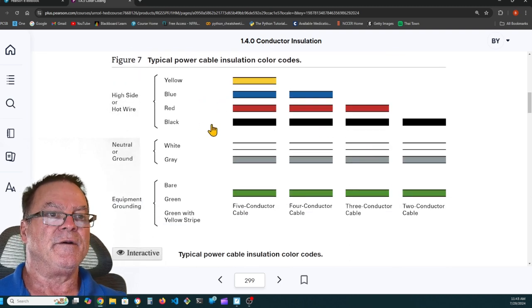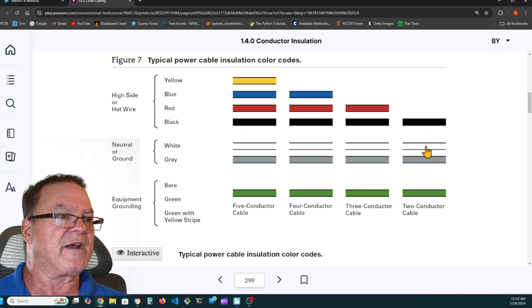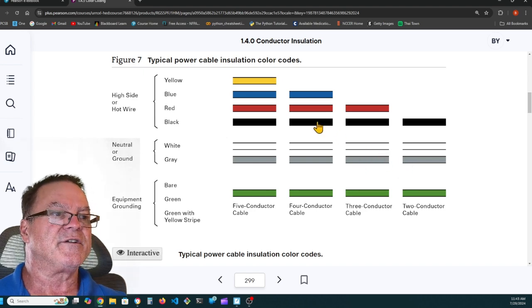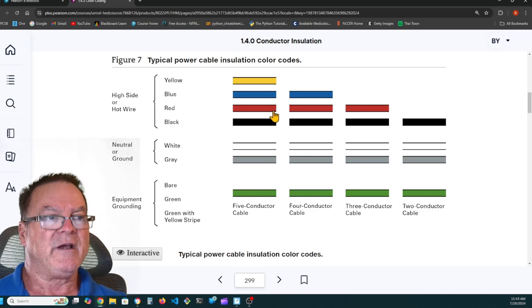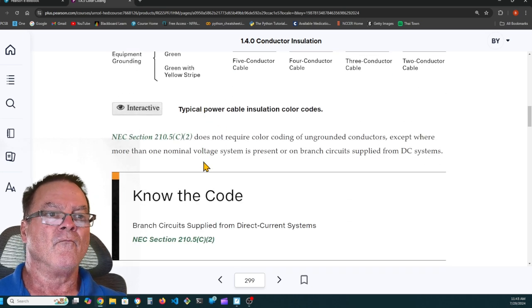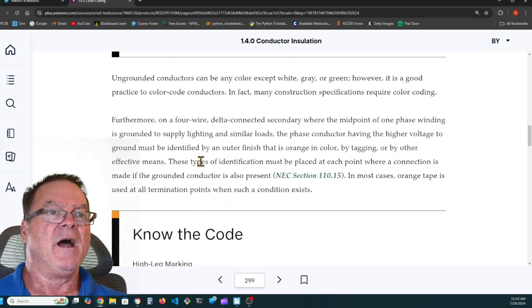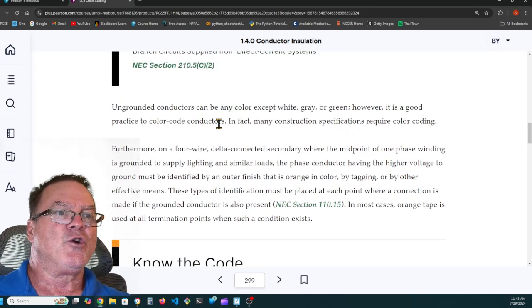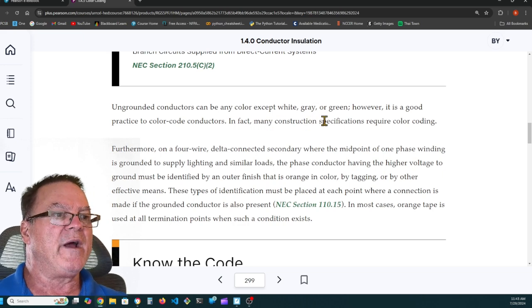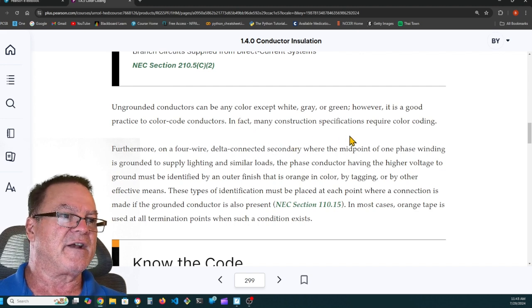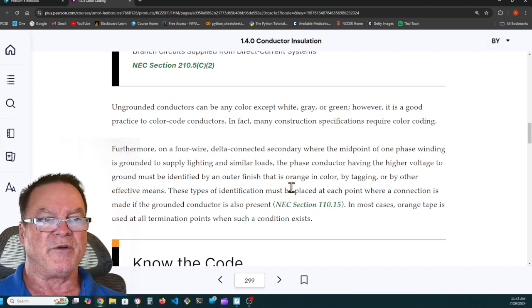So here is their breakdown. So 2 conductor, you have black and white. 3 conductor, you have black, red, white, or gray. 4 conductor, you have black, red, blue, and white, or gray. And 5 conductor, you have black, red, blue, yellow, and white, or gray. Ungrounded conductors can be any color except white, gray, or green. However, it's a good practice to color code conductors. In fact, many construction specifications require color coding.